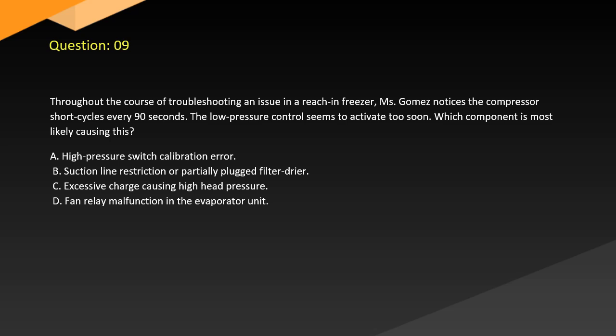Question 9. Throughout the course of troubleshooting an issue in a reach-in freezer, Ms. Gomez notices the compressor short cycles every 90 seconds. The low-pressure control seems to activate too soon. Which component is most likely causing this? A. High-pressure switch calibration error. B. Suction line restriction or partially plugged filter dryer. C. Excessive charge causing high head pressure. D. Fan relay malfunction in the evaporator unit.